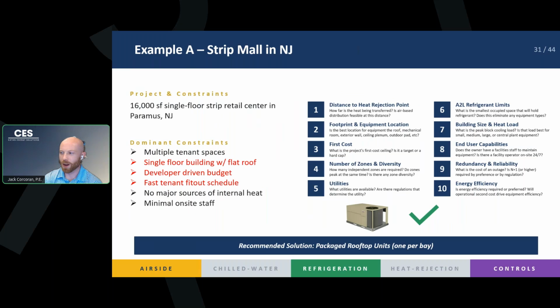This is pretty much a bread and butter rooftop unit situation, right? A single floor means your roof has easy access into every space. Cheap and a fast schedule. Rooftop units are pretty much going to be the best option here. You want to stick a couple of them on the roof, right? Maybe you want to have one per tenant, because maybe one tenant wants it to be hotter or cooler than the others, and you want to give each one of them their individual controls. So in this situation where we have a one-story, fast, cheap project, go with rooftop units. You're not going to go wrong. They're flexible and will be able to make it work.